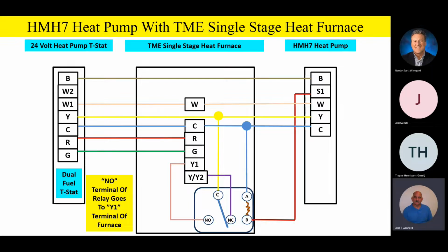So it will drive it to the highest airflow. Let's say we have a Y2 call on there because the compressor's running outside. We go into defrost, and then we call for a W call as well. The ECM motor, because all these E type of products, TME, the AE, and so on, are all ECM type motors. Let's say the cooling airflow, the Y airflow, is higher than the heating airflow on this furnace. It'll stay on the cooling airflow. If the heating airflow, when you get a W call, is higher than the cooling airflow, these ECM type motors always take the highest airflow command they're receiving. So even though you might have Y cooling airflow, say 1200 CFM on a 3-ton unit, maybe the heating airflow on this TME furnace is 1400 CFM. If it sees a W call, it'll drive it to that 1400 CFM.